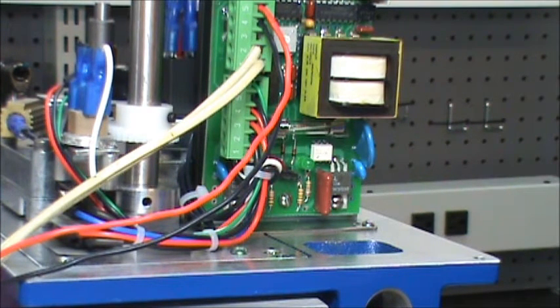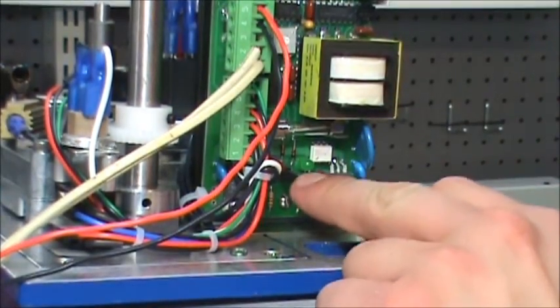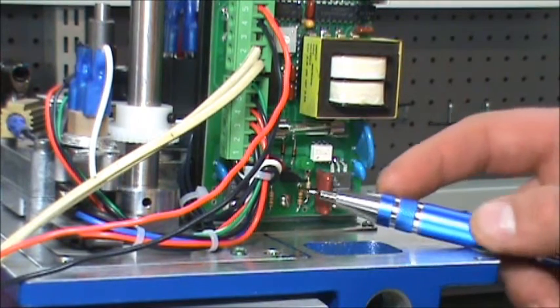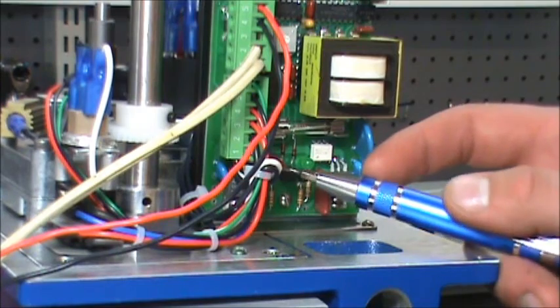If you want it to fail in the open position, you'll take the jumper, turn it sideways. I'll get my hand out of here in just a second. And you'll put it on the middle and left-hand side towards the red.